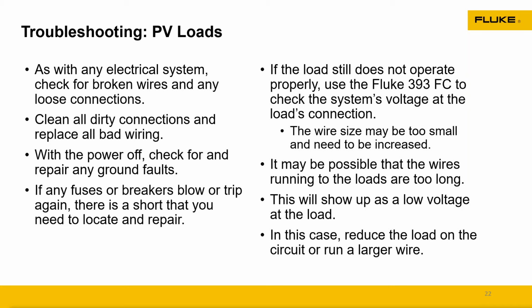We were megging out the wires. We were looking at what that number looked like. Come to find out, when they buried that line, somebody had nicked one of the conductors. Once it got heated up and started working right, it shorted out and the system shut down. It was keeping the load from continuing to do its job. So again, recognizing that, knowing what tools, that technician went through that whole system and finally determined where that problem was persisting between the inverter and the step-up transformer.